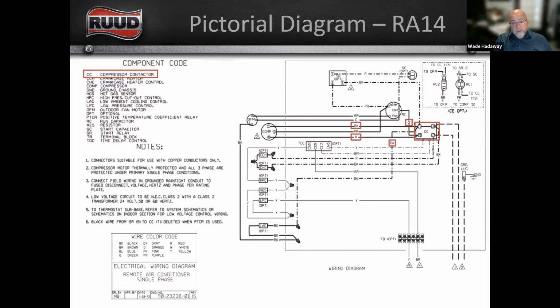Then, possibly, right, this dotted line lets you know that that is an optional wire, or something that you might not see in every unit, depending on model number and features. And then that black wire is going to wire into some other optional components, if they're there, right? Like a crankcase heater, crankcase heater control, high pressure control, hot gas, and then low ambient control, which would all be listed on the component code over on the left, whether that is in that unit or not.